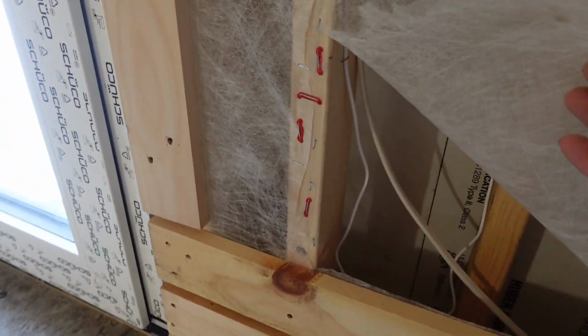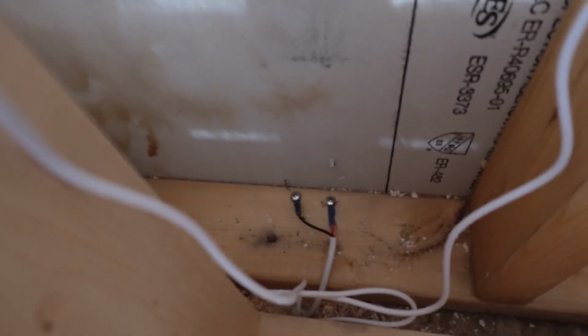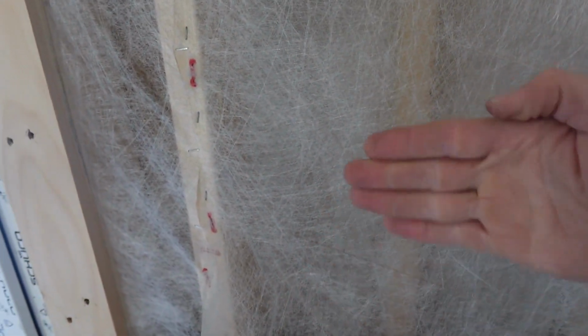Got another sensor in here with 3 probes. So there's a moisture probe down there. There's a temperature probe on the outside surface of the wall, so I'll measure the outside face of the wall. I'll be able to get temperature from the inside face and the outside face, so I can measure the delta between interior and exterior of the wall, as well as humidity, dew point, moisture content.